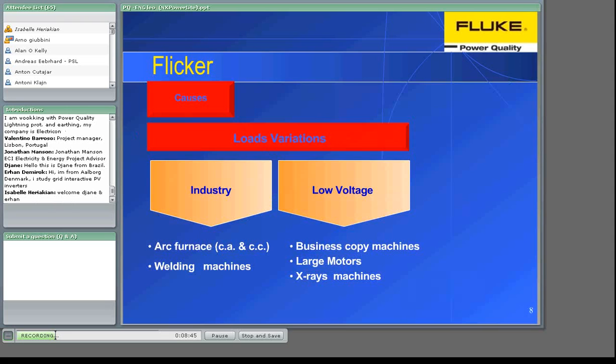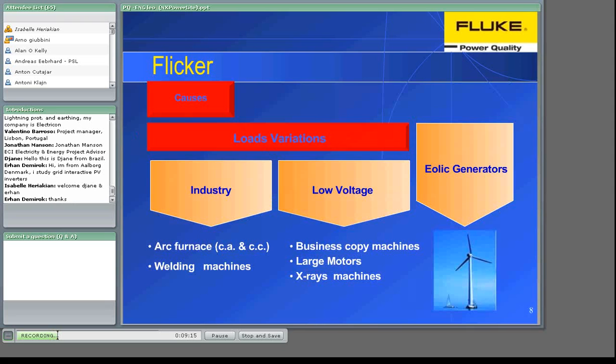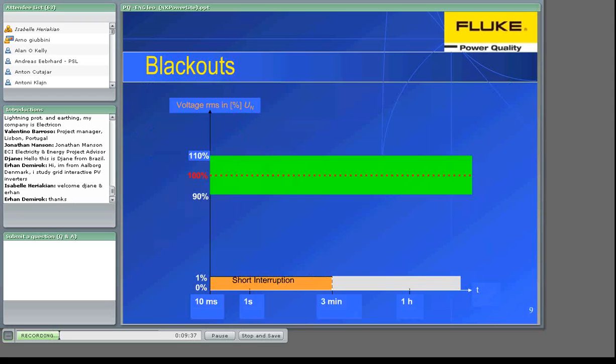Causes of flicker. At the medium voltage level, we have arc furnaces, welding machines, and induction furnaces, which are large metal melting systems employing irregular powerful arcs to generate heat. At low voltage level, instead, switchings of heavy loads related to the line impedance can generate flicker. At the generation side, wind energy systems are also known as flicker producers. The energy generation, we can say, depends on the wind's mood. Just consider that this kind of generation is increasing at a rate of about 30% per year.